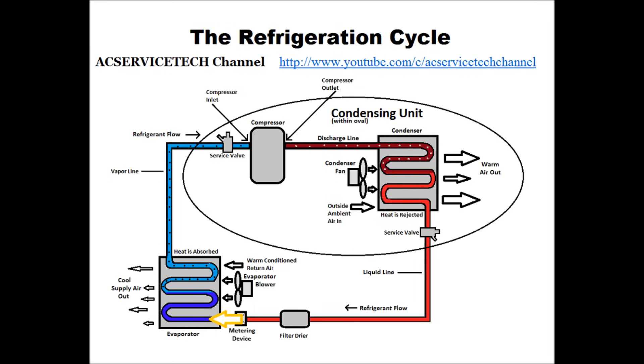Until it gets to the middle of the evaporator coil, the refrigerant is actually absorbing heat. As it absorbs enough heat, it turns into that saturated state in the middle of the evaporator coil, where most of the energy absorption is taking place. Right after that is where it turns into a low pressure, low temperature vapor. Right after the saturated state it turns into that low pressure, low temperature vapor, and until it comes out of the evaporator coil it's still absorbing heat.